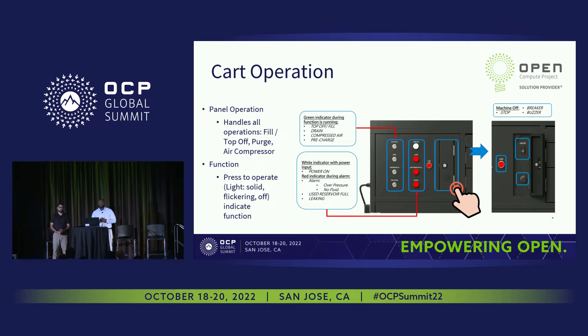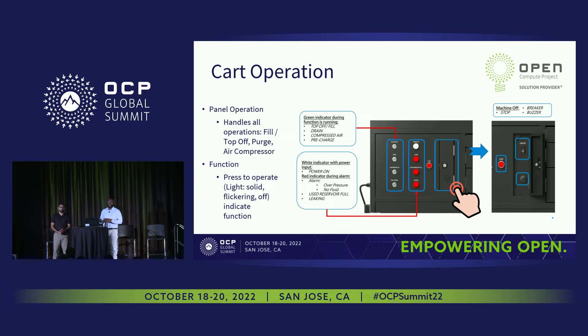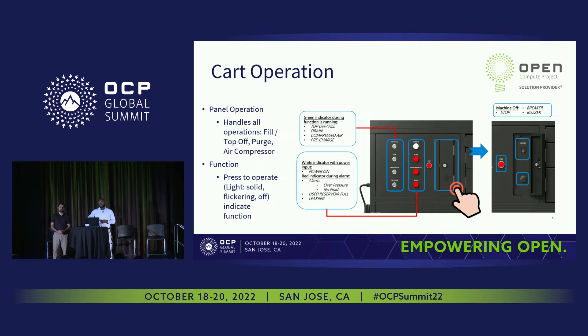The cart operation is meant to be as simple as possible. The switches are push switches — all you have to do is press them and the operation will begin or stop. There are three indications: a steady light showing the operation is currently happening, a blinking light indicating the operation is completed, and a red light indicating warnings of overpressure or a leak inside the system. There are also warning lights on the right for those red warnings. On the far right is the power panel, which has a key so it can be locked for security to designate who can use the cart. Additionally, highlighted in the blue box, there's an emergency stop button — if the tech feels it's unsafe or doesn't want the operation to continue, they can press it and the cart will stop immediately.